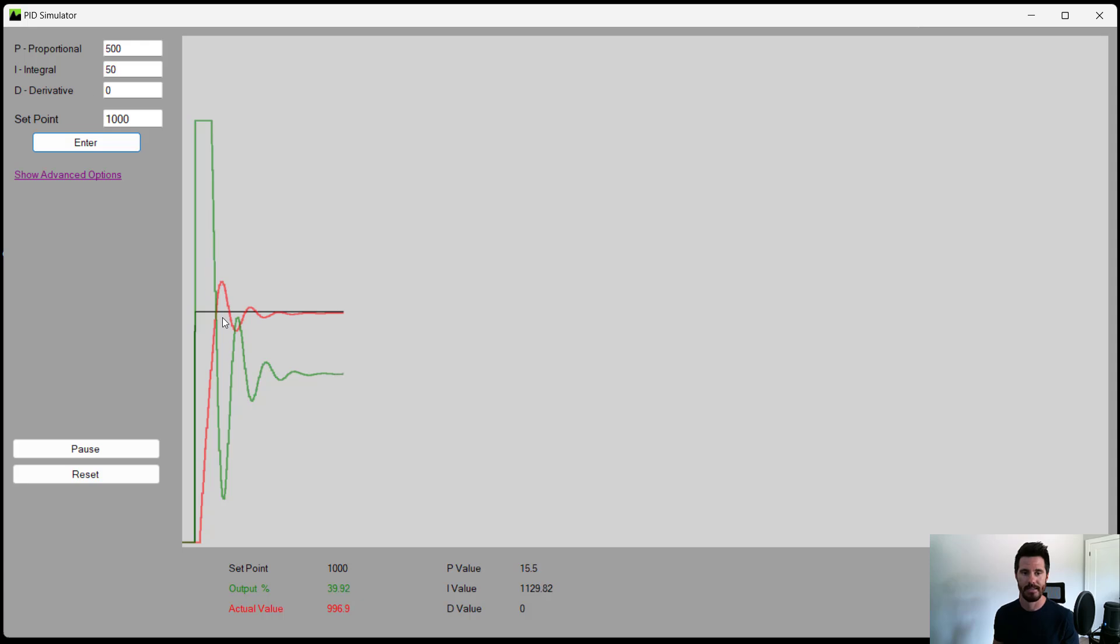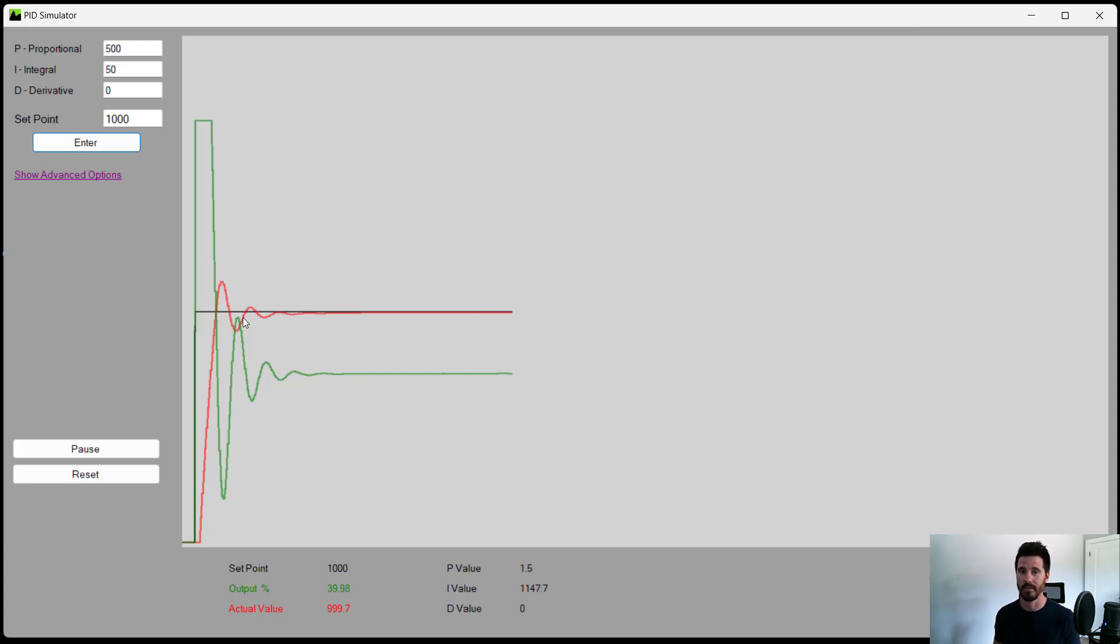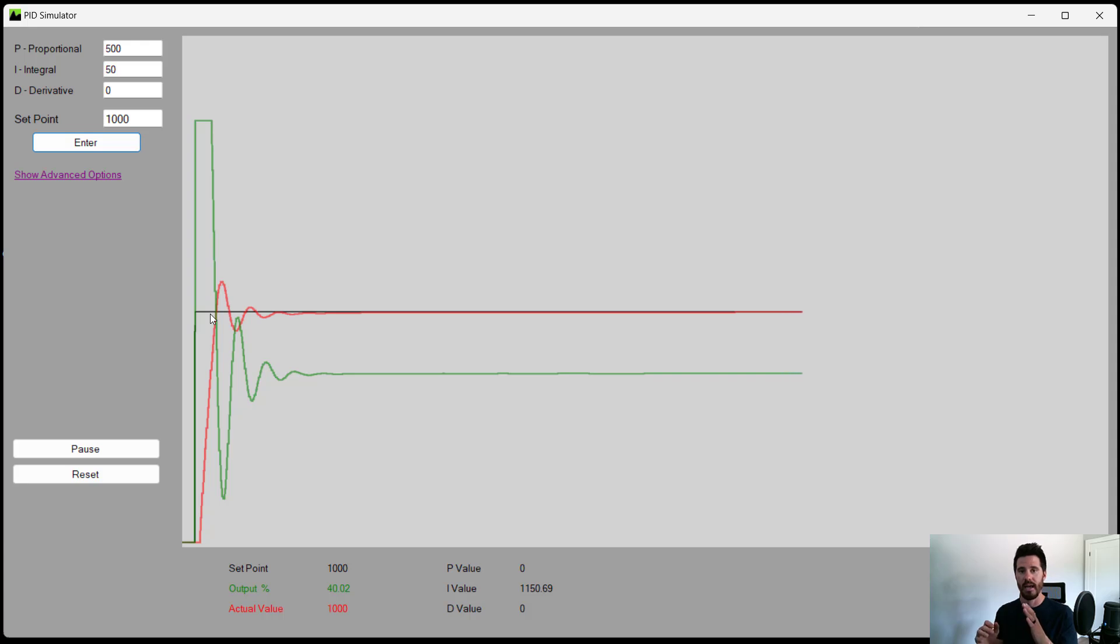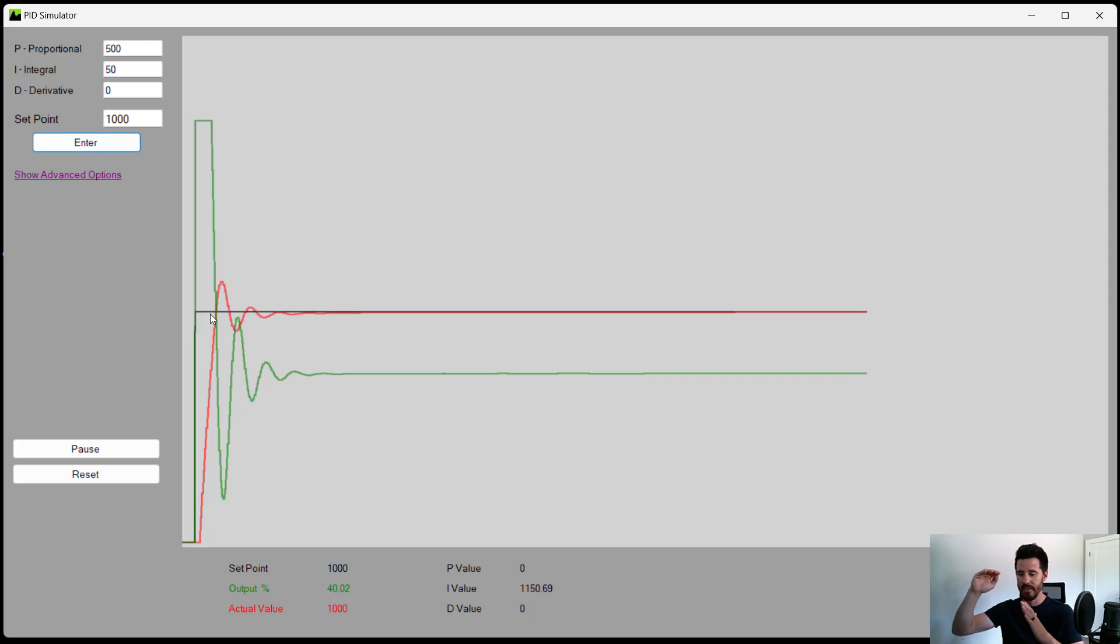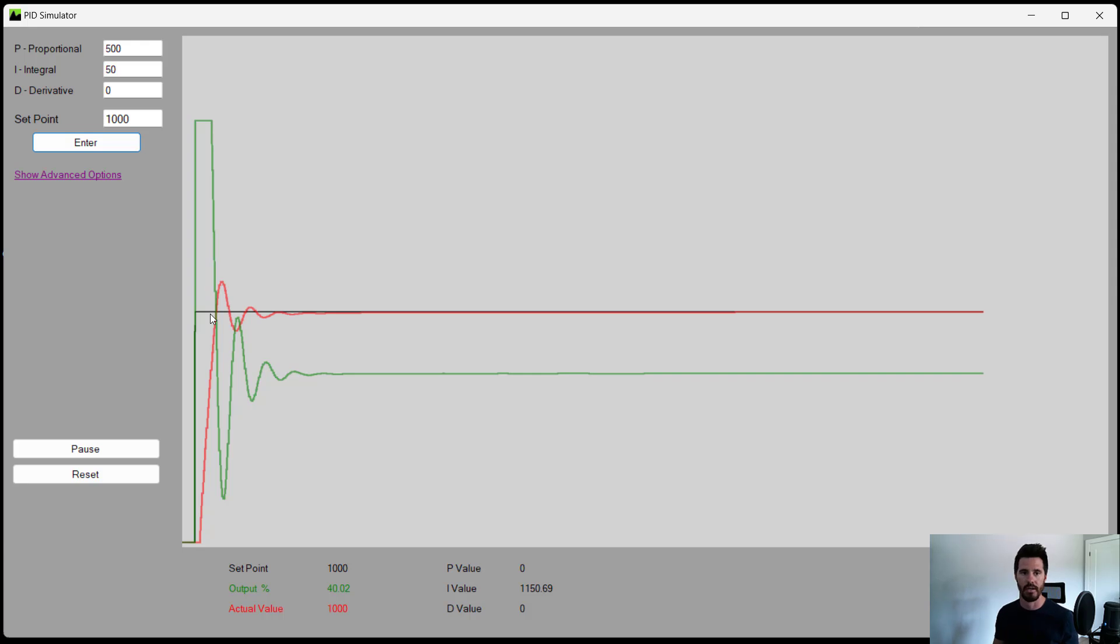The derivative is meant to take this initial overshoot or undershoot and pull it back to stop it from overshooting as much. If you have too much of a D value, it actually pulls back too much on the controller and makes it unstable. So the D value is the last one that you want to tune or the last one to look at. And if you're not sure, it can always be set to zero. So anyway, the derivative value or the D, what it looks at is how fast is my output reaching my set point. And if it sees that ramp is really steep or really fast, then the D is going to start pulling back on your output to limit that actual value from overshooting the line.